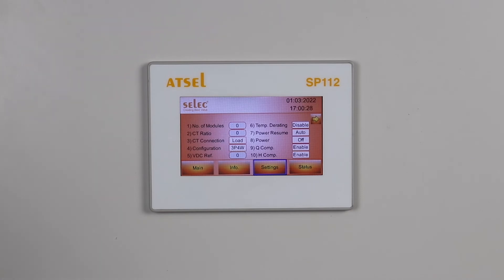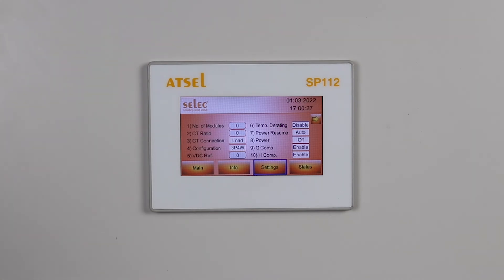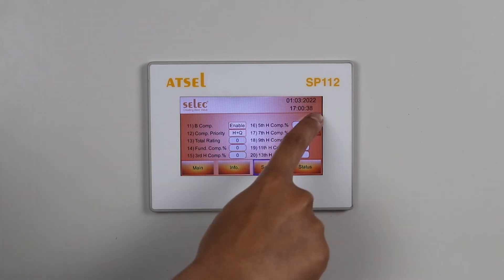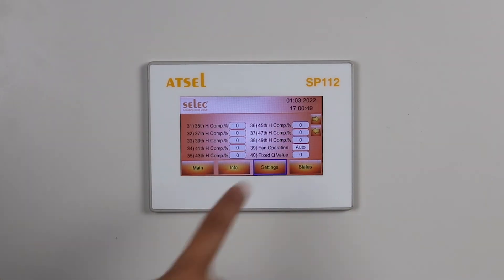Configuration can be set to 3 phase 3 wire or 3 phase 4 wire. Internal VDC reference is currently set to 740; one can set it to 760 depending upon the site condition. Temperature derating can be enabled or disabled. Reactive power (Var) compensation can be enabled or disabled. Harmonic (H) compensation can be enabled or disabled. Balanced (B) compensation can be enabled or disabled. Fundamental compensation sets what percentage of fundamental compensation you require. Similarly, you can set individual harmonics. The ASVG will compensate harmonics up to the 49th order.